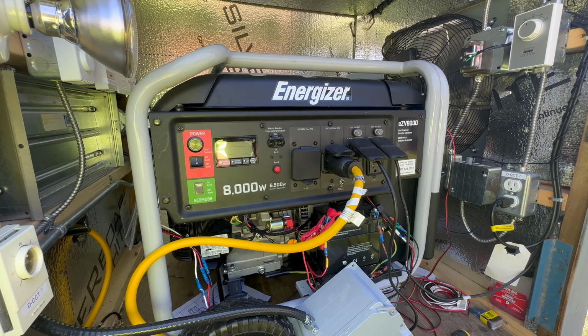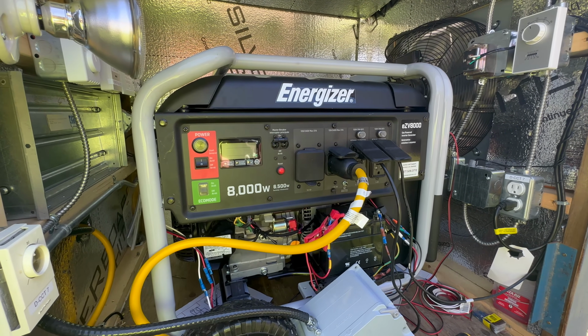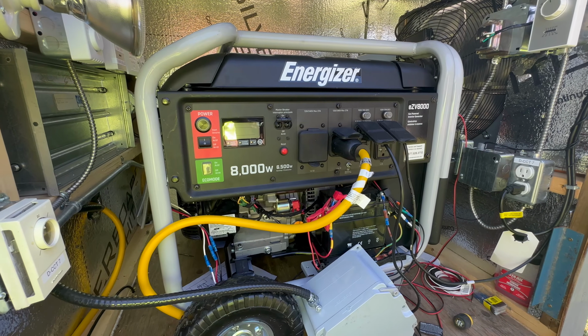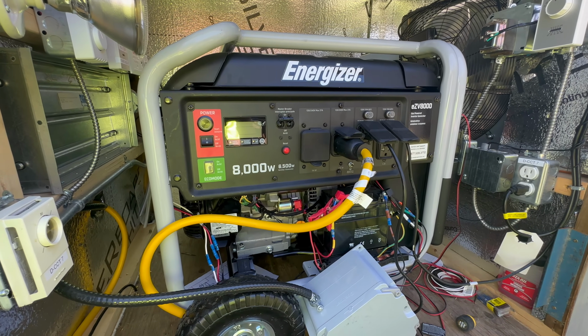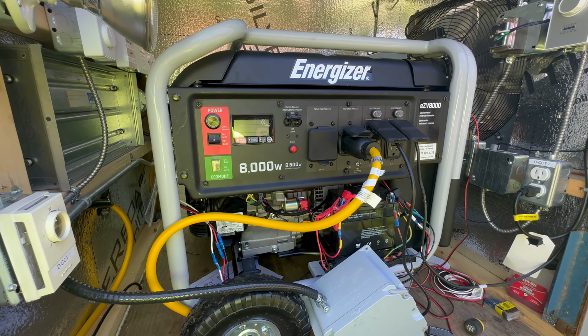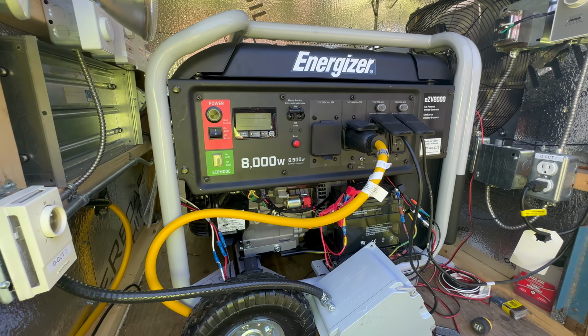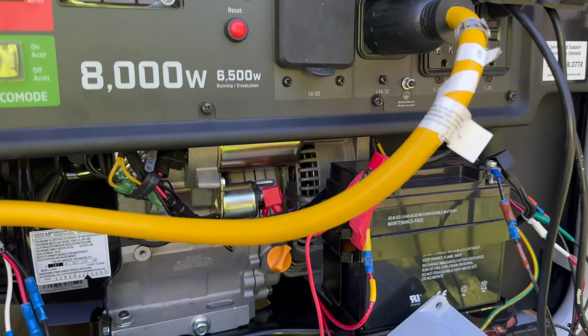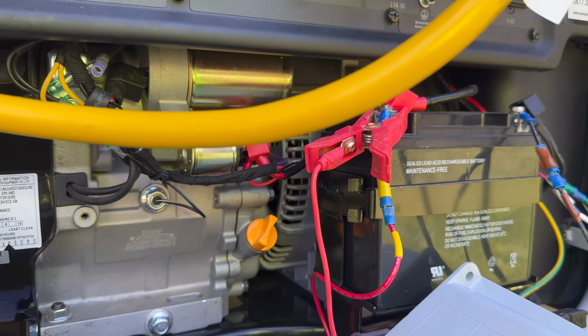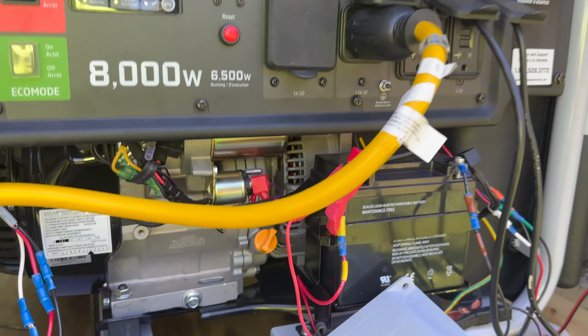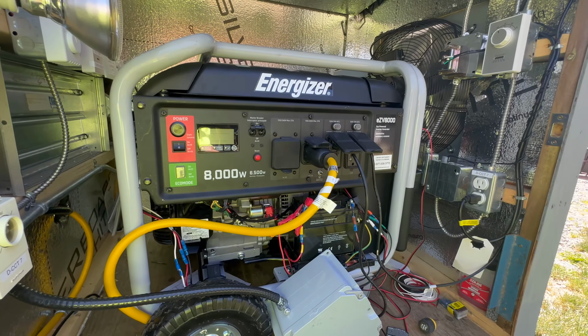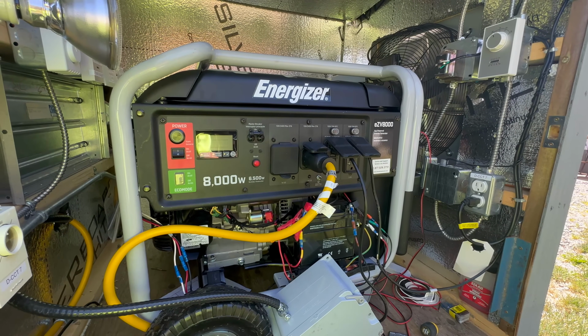I believe that is under 3% total harmonic distortion, which a standard generator that is not an inverter type will put out a much higher total harmonic distortion, which could be damaging. Inverter generators, the actual alternator inside off the engine puts out DC current, and then the inverter turns it into AC, which has a much cleaner sine wave.